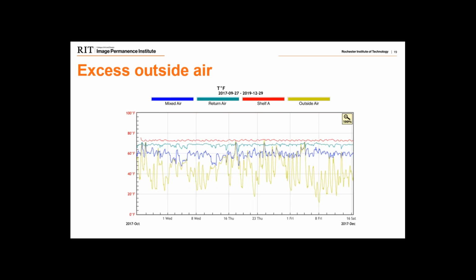Having worked in this facility, we talked to the facility staff, and we were able to find out that they were using a very large amount of outside air for an unoccupied collection room. We were able to reduce that, save a little bit of energy that's being used, and narrow this gap a little bit. So we're not lowering that temperature so much and reheating it, losing some energy in that process.